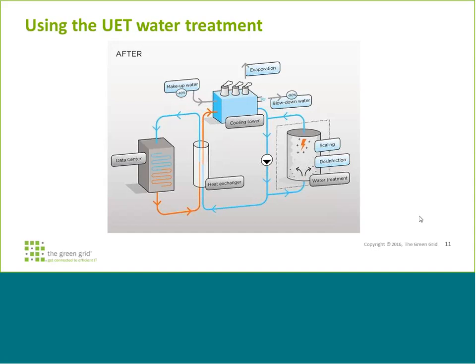Yeah, well, we can't do anything about the evaporation amount. That's the cooling principle itself. So we evaporate the same amount, but if you look at the blowdown water, you see a minus 90% over there. And as it turns out, we are discharging less than 10% of what we used to discharge before, which means that the makeup water goes down with 40%. So we discharge only less than 10% of the makeup water, which is excellent, nowhere to be seen in the world, on simple, untreated city water as makeup water.